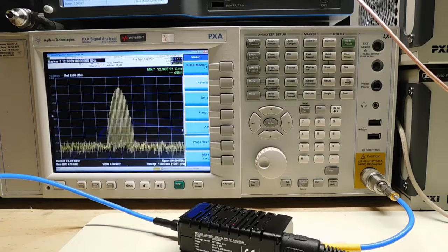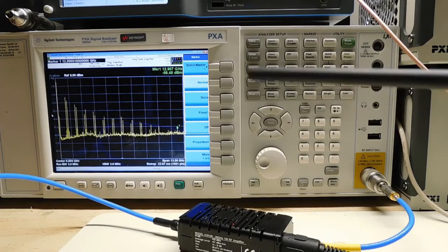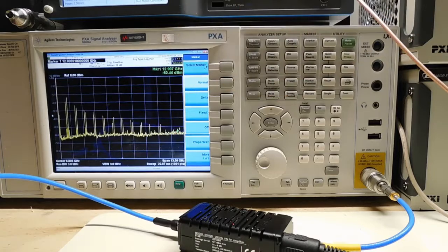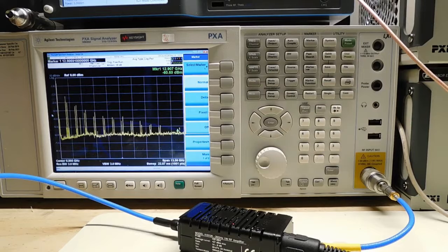The first thing I want to do is change the span of the spectrum analyzer to full span. This is a 13 GHz spectrum analyzer, so the sweep we see going across there is all the way up to 13.5 gigahertz, I believe. Right at this side we can see the 75 megahertz fundamental frequency that I created, but also because our clock frequency is set to 1 gigasample per second, I get plus or minus 75 megahertz at 1 gigahertz, 2 gigahertz, 3 gigahertz, 4 gigahertz, 5 gigahertz, 6 gigahertz, and so on. And these are our Nyquist bands.